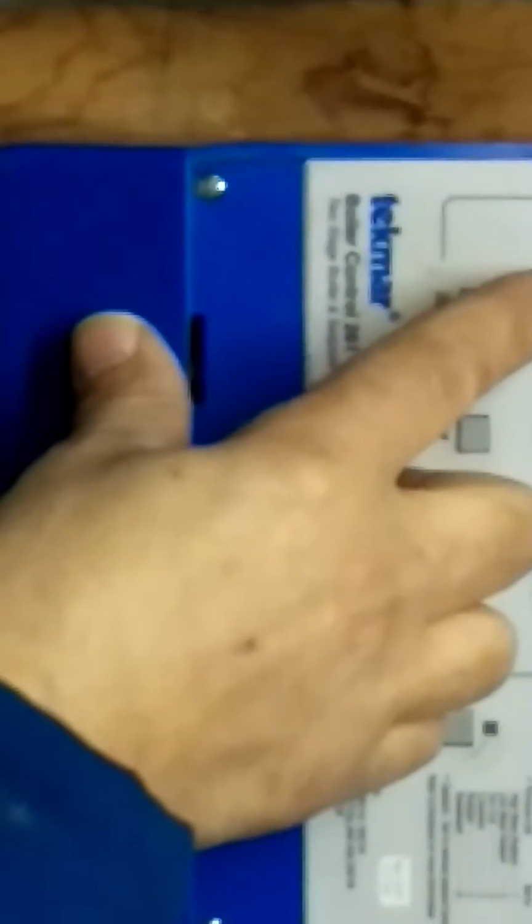Basically the adjust, so it's more like set point, but I've got that at 185 on the adjust side. But don't worry about that. Boiler indirect is always going to be at 70, otherwise it throws a curveball. So boiler INDR, always at 70. The next one is boiler design, DESIGN, and we've got it at 185.